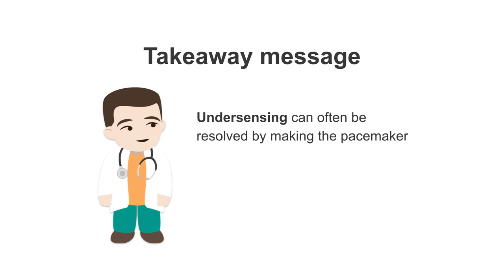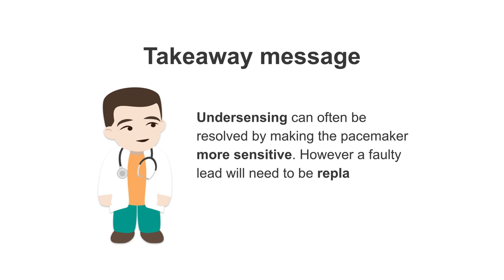So, your takeaway message: under-sensing can often be resolved by making the pacemaker more sensitive. However, a faulty lead will need to be replaced or repositioned.